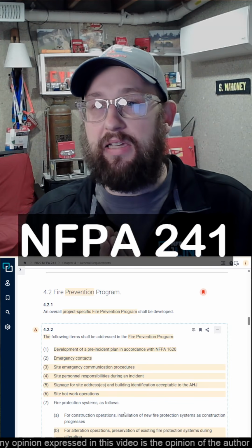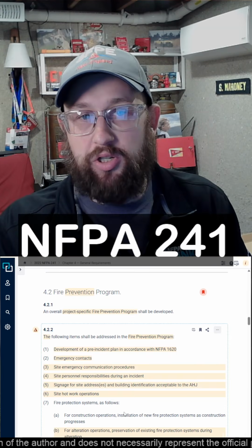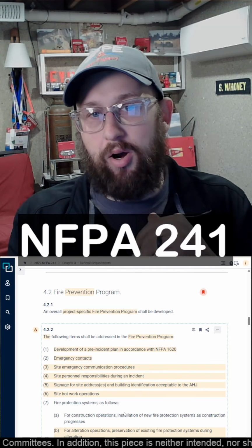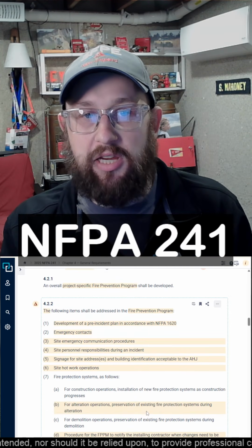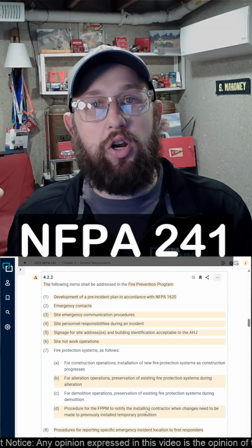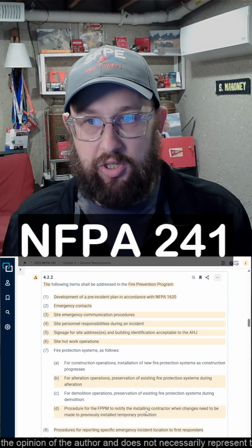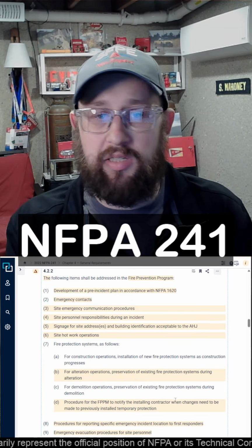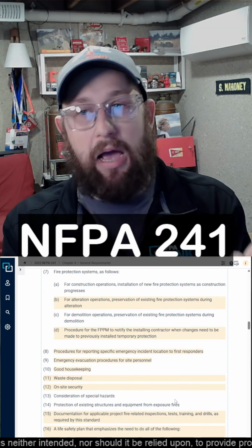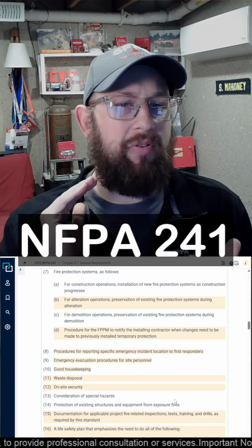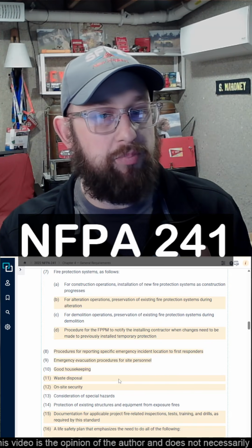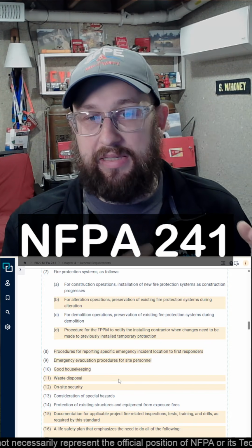And they address things like having proper emergency contacts, proper pre-planning for the responding fire department, emergency communication procedures. We want proper signage in the building. We want to know how we're handling hot work operations. What type of fire protection systems are going to be in place in the building? What are we doing as far as housekeeping? We're providing fire department access. How is that being provided? What's our waste disposal at that site? And what does that look like?